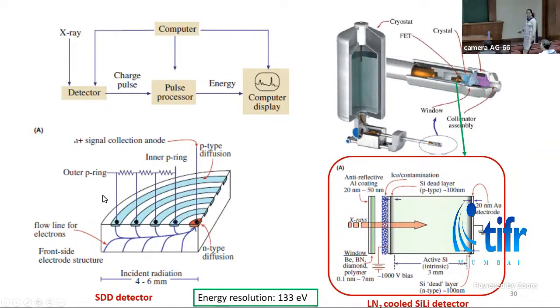These are the new generation detectors, which are SDD, silicon drift detectors. Here on N-type silicon, there are P-type diffusions made in a concentric ring type fashion. So this geometry helps to give more throughput. That means more electron hole pairs are created by the number of photons as compared to this detector. This also works at comparatively higher temperature compared to this, so it doesn't need liquid nitrogen to be cooled with. And the biasing voltage needed for this detector is 4 times lower than this one. EDS has a resolution of 133 eV.